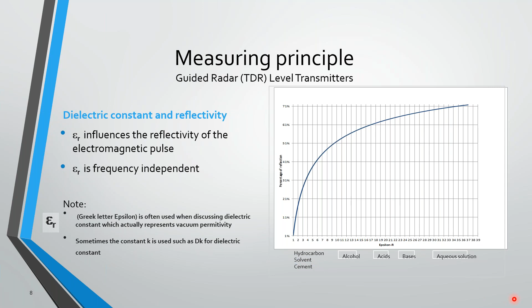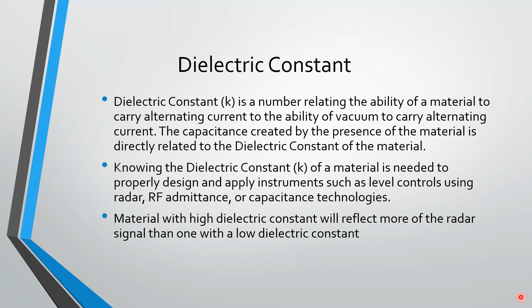So again, dielectric constant is a number representing the ability of a material to carry alternating current compared to the ability of a vacuum to carry alternating current. They look at the difference between those two and come up with a number. We need to know this number to properly design a level measurement system using this technology. Higher dielectric reflects more signal, lower dielectric reflects less signal.